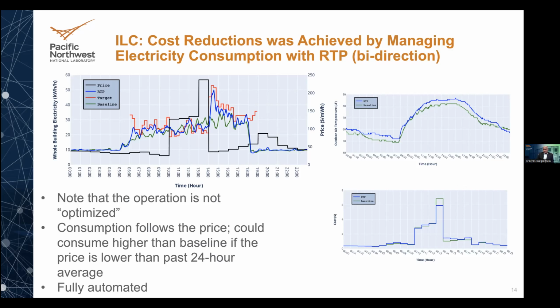And then the whole building consumption is shown on the primary y-axis on the left. That graph also compares consumption for 2 days. Baseline day with normal operations is in green. And then the RTP day, when the RTUs in the building are responding to the real-time pricing signal, the consumption is shown in blue. The price signal is shown in black on the secondary y-axis. Before each hour, when the price of electricity for the next hour is known, ILC computes demand flexibility, or the target consumption for that hour, which is shown in red.